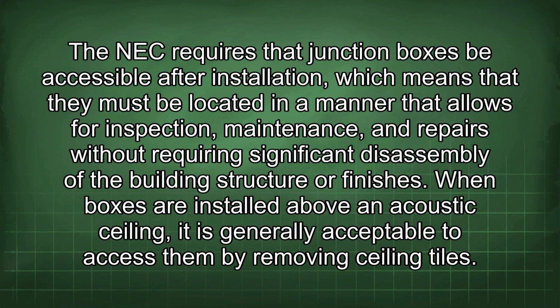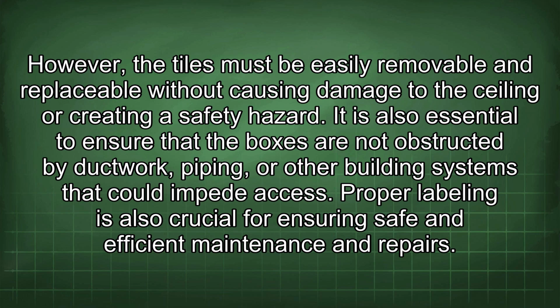When boxes are installed above an acoustic ceiling, it is generally acceptable to access them by removing ceiling tiles. However, the tiles must be easily removable and replaceable without causing damage to the ceiling or creating a safety hazard. It is also essential to ensure that the boxes are not obstructed by ductwork, piping, or other building systems that could impede access. Proper labeling is also crucial for ensuring safe and efficient maintenance and repairs.